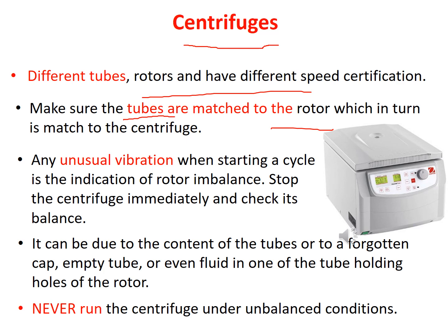Since, as I mentioned, their speed is very high, this is really important while you are using them. Let's say you are going to start, and you feel unusual vibration, because for example you are going to centrifuge at 1000 rpm, 13,000 rpm, or 15,000 rpm, spinning your solutions or any chemical or extracted material. Once you start, if you feel an unusual vibration, it means there is a problem. Sometimes the chemicals are not balanced, or there is uneven balance or uneven composition, or the number of samples can produce this unusual vibration. At that moment, just stop the machine and double check.